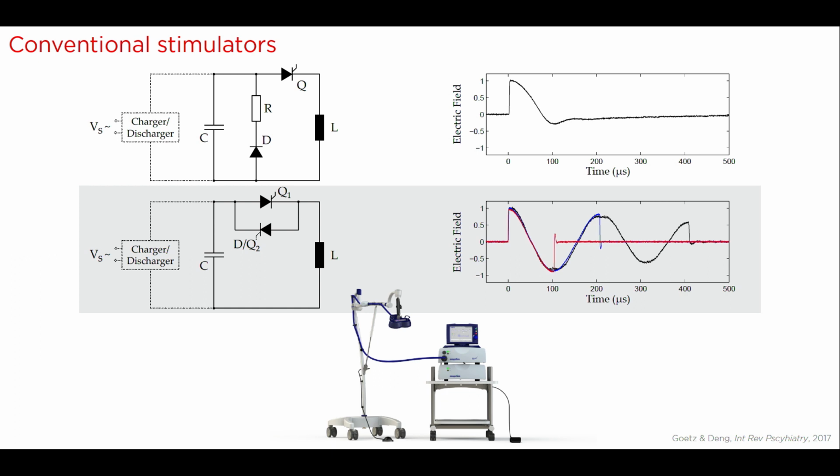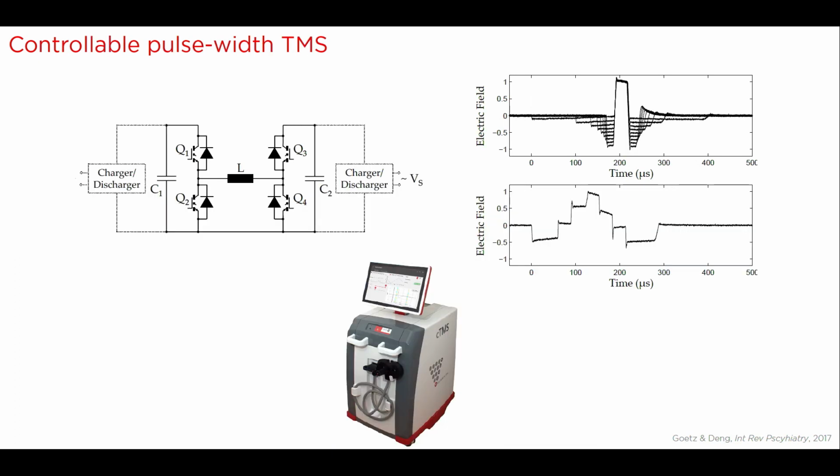Now it turns out that the brain and neurons are not as responsive to sinusoidal waveforms. Neurons in the brain much prefer square waves. This has something to do with the membrane of the neuron acting as a capacitor connected in series with extracellular and intracellular resistance, serving as more or less an RC circuit.